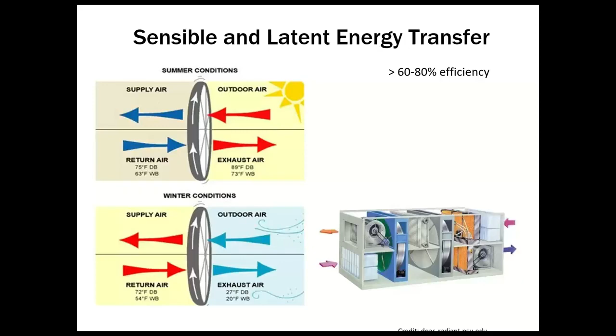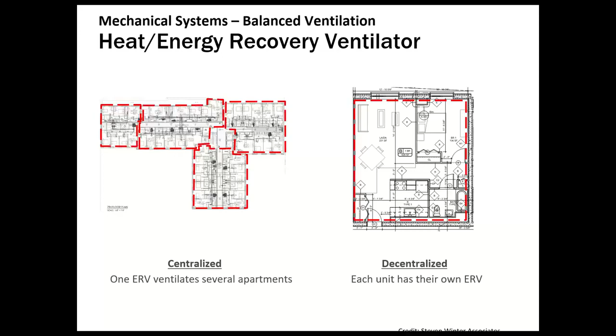Again, as with the heating and cooling systems, we can do centralized or decentralized type systems. Centralized, perhaps covering a number of apartments or floors or the whole building, versus the unit by unit type. And of course, there are benefits in design and constructability for each of those. And I won't list them all, but essentially, we certainly do see benefits in the centralized systems in terms of fewer wall penetrations, but are challenged because we have more vertical shafts and perhaps more horizontal distribution, floor-to-floor height requirements, and of course more ductwork that needs to be sealed and fire rated with dampers.